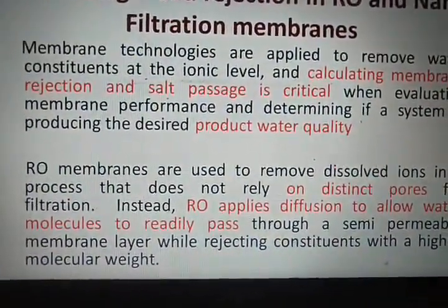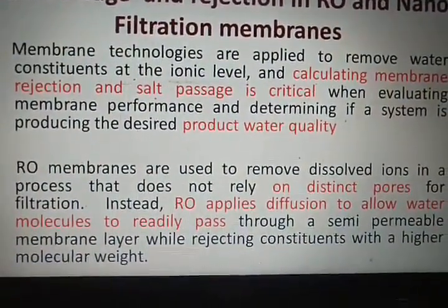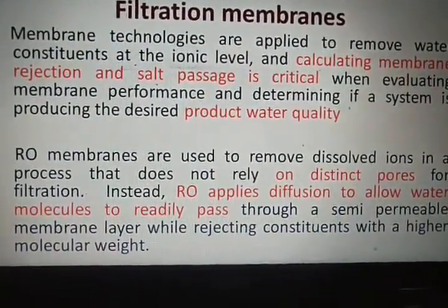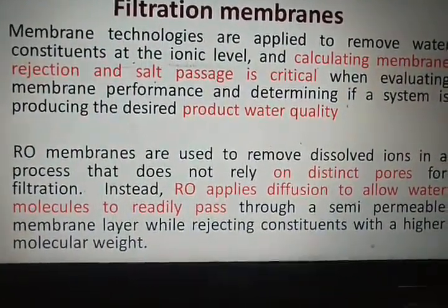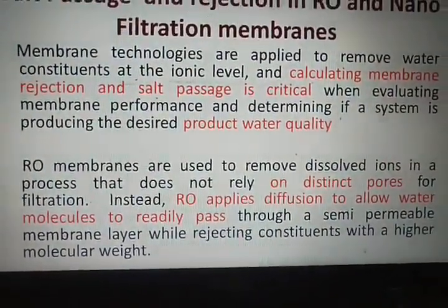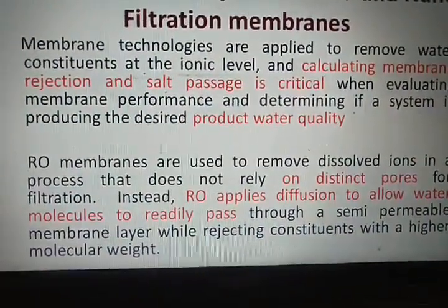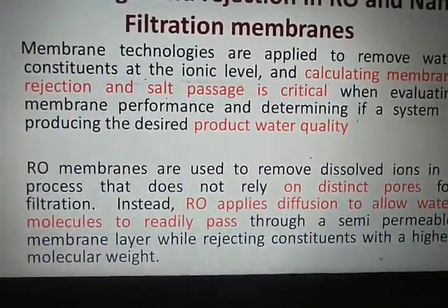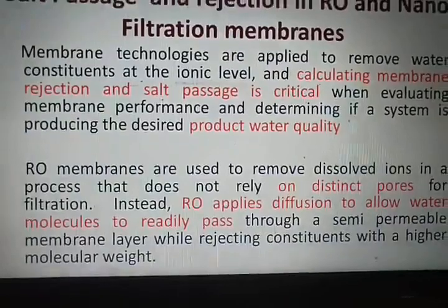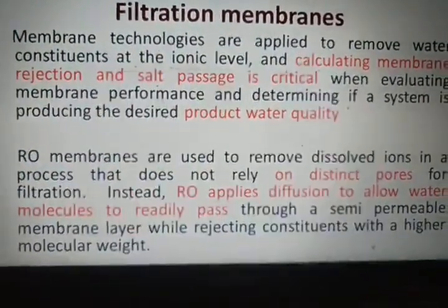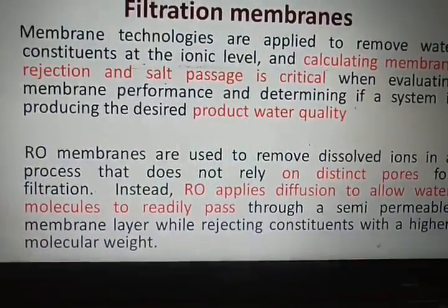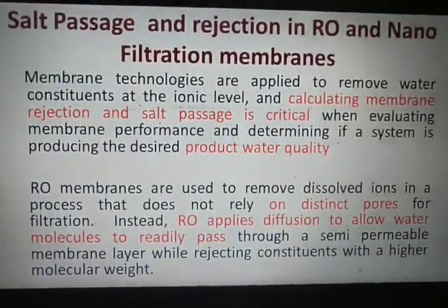RO applies diffusion technology, allowing water molecules to readily pass through a semi-permeable membrane layer while rejecting constituents with a higher molecular weight. That is the important difference: ultra and microfiltration rely on distinct pore technology, whereas RO and nanofiltration work on the principle of diffusion.